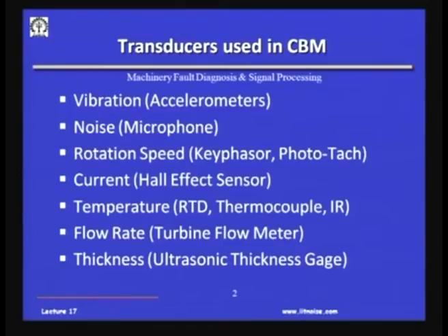So, from outside, how do I know that such a buildup has occurred in the inner walls of the pipeline? This could be very easily measured online by an ultrasonic thickness gauge. Sometimes people even do a portable X-ray radiography of the tube from the outside, particularly in boiler tubes, when there is a lot of scale formation because of the water flowing through the pipelines.